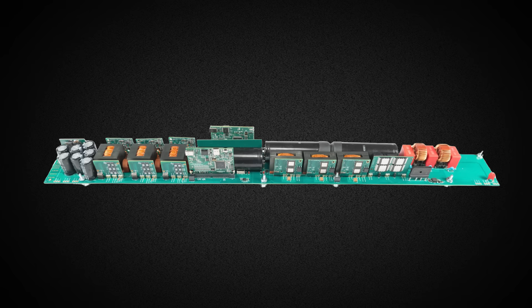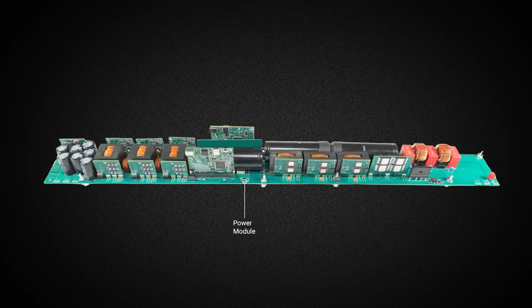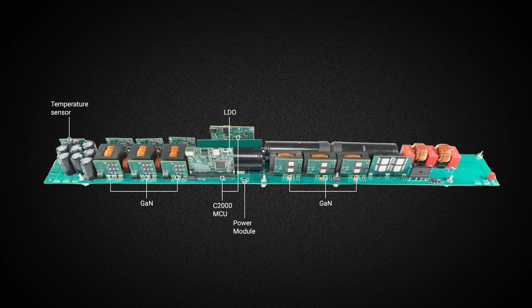First, let's look at an example 8 kilowatt PSU that's used today to power 125 kilowatt racks. This has a single phase AC input and a 48 volt DC output, and it shows what a PSU module in a power shelf looks like. Now, this design is uniquely enabled by TI's broad portfolio of analog and embedded products. This design leverages over 15 devices from TI, ranging from gallium nitride power stages and C2000 microcontrollers to digital isolators and high-speed op-amps. The next generation of server PSU designs for AI compute loads looks something like this.